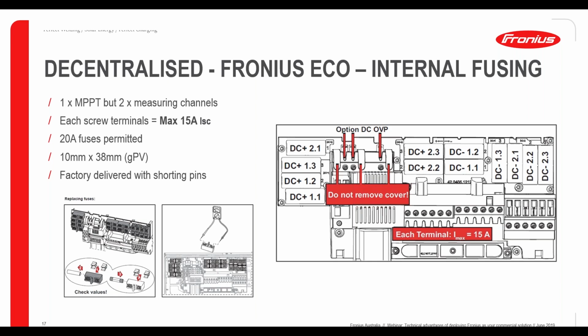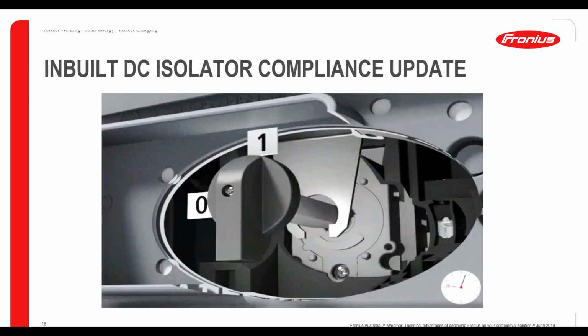So just a little bit of an update on the inbuilt DC isolator compliance side of things. It was disputable in the past whether any connections above 4 strings, so either 5 or 6 strings connected to a Fronius Eco inverter, would or would not require external DC isolators. The good news is with Amendment 2 happening this week, we will have the potential to use the DC isolator in all different scenarios and configurations with our inverters.